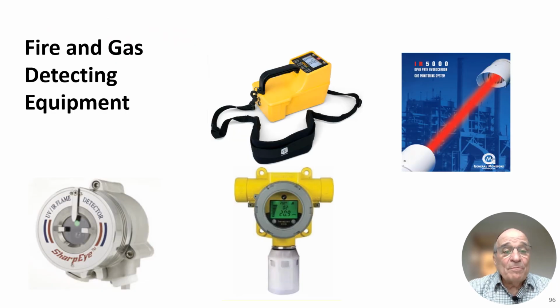Keep in mind, there are many types of hazard detection pieces of equipment in a plant. You can have an oxygen sensor. You can have a fire detector. This is a portable gas detector. This is a fixed position type of gas detector. This one happens to be an open path gas detector type that will look across a large area, let's say across 100 foot of plant area, and look for gas leaks that might be occurring somewhere within that 100-foot zone. And there are many other types of hazard detection devices within a plant, cold sensors, etc.